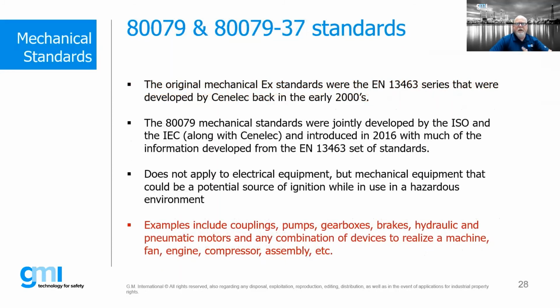Now, the mechanical standards - we'll talk a bit about this. This is causing a lot of heartache for people right now because they're fairly new. They were jointly developed with ISO and Cenelec and introduced in 2016. The information in the 80079 standards was based on the Cenelec standards, in this case the 13463 standards. So this doesn't apply to electrical equipment, but now applies to mechanical equipment that could be a potential source of ignition while in use in hazardous areas.